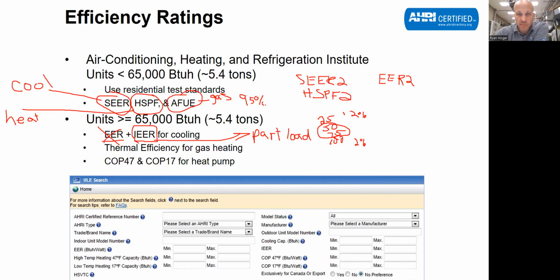I'm realizing this slide is becoming a sloppy mess right now. And then for your packaged equipment with gas heating, maybe you have an 82% efficient rooftop unit or something like that. For packaged rooftop units, it's going to be really hard to find anything above 84% efficient. There are a couple units out there, but the challenge is once you get above like 86% efficient, you start condensing in the flue gases, which means the condensate line. Well, a condensate line on a roof outside in the winter in places where it gets below 32 degrees is an issue. It freezes, and that becomes a problem.